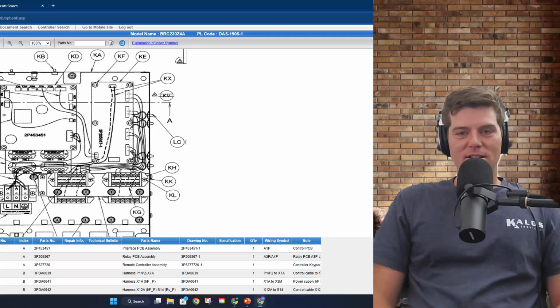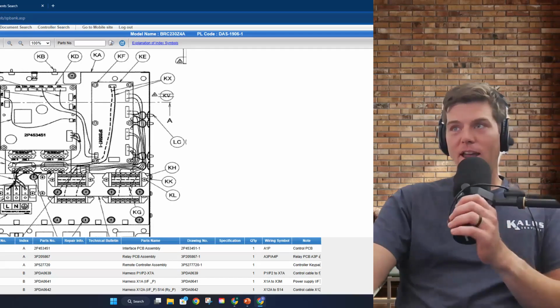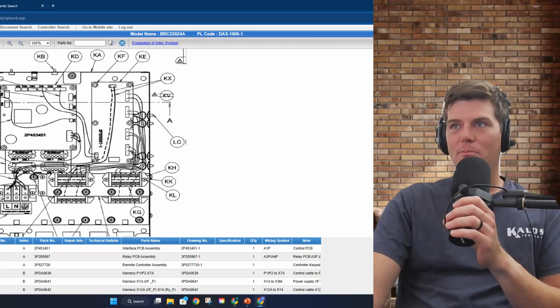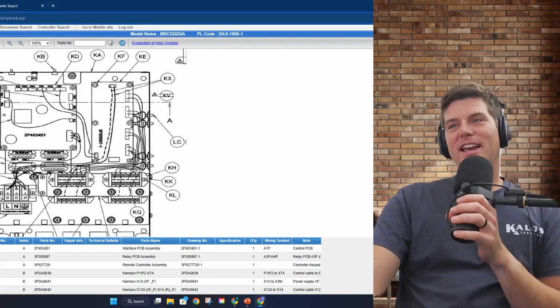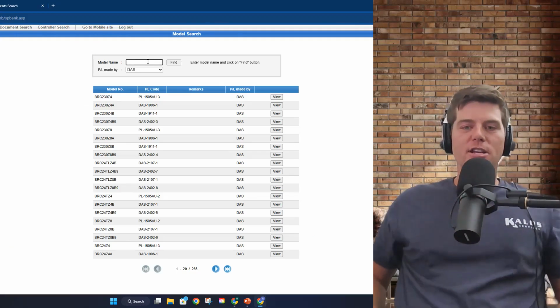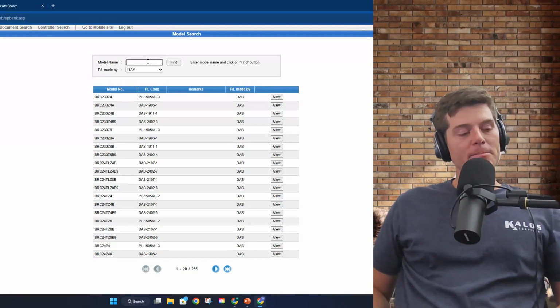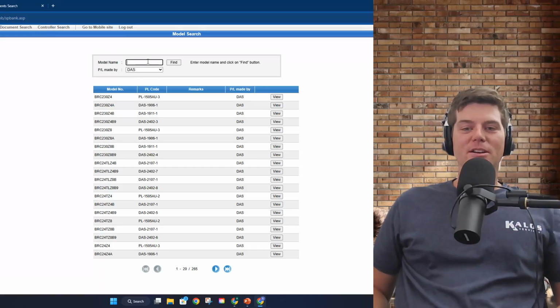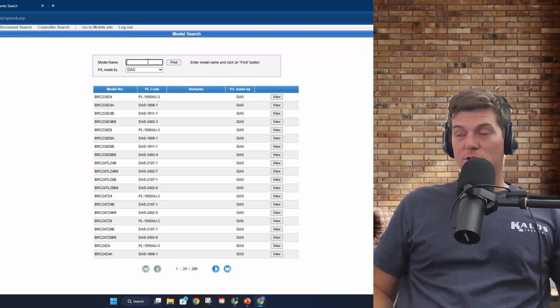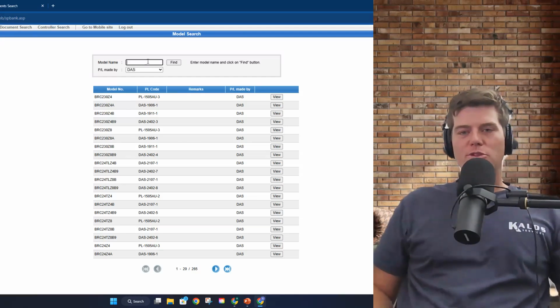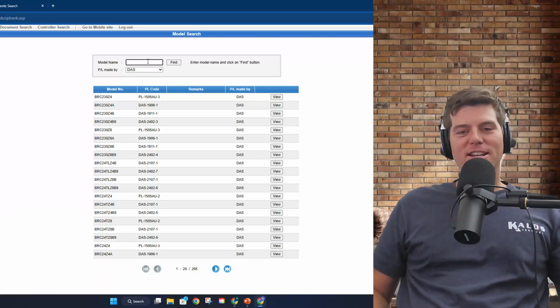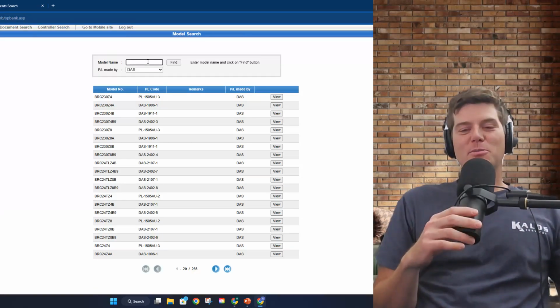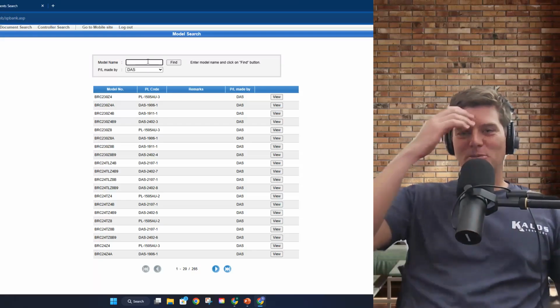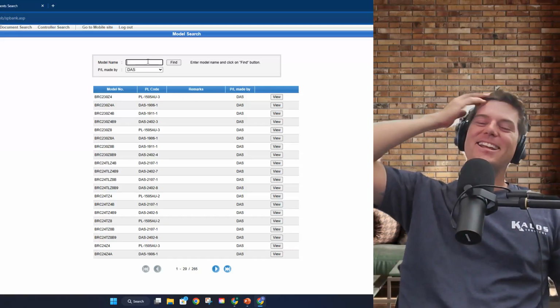What's that? What's the model number for that one? But with that, they have the - what is it - the Shirudo technology, which came out like 3 or 4 years ago. Someone's gonna correct me - it's isolation valves at the indoor unit, BS box in the outdoor unit. The outdoor unit will actually pump itself down if it senses an R32 leak in the space, and they coined it Shirudo technology. I could look up what the term actually means, but it was this whole philosophical approach to it. The reason I remember is, if I tell you exactly what it looked like - it was a bunch of superheroes. Do you remember when I shared that? It was a bunch of Daikin superheroes with capes and stuff. That's how they were marketing it, to save the day.